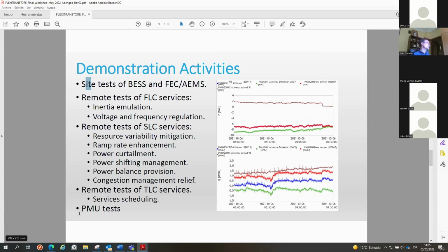In parallel, the phasor measurement units were tested, and it was possible to compare the results of the PMU measurements against the measurements taken during the test, which also served to verify the phasor measurement system.